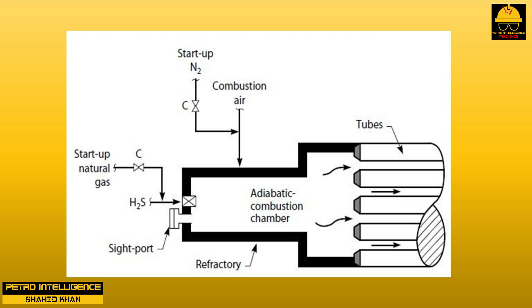Basically, the other people at the sulfur plant were head office people whom he did not trust. The reheat phase of the start-up seemed to be going quite slowly. The combustion chamber temperature crept up by 50 degrees Fahrenheit an hour, rather than the normal 150 degrees Fahrenheit per hour. To speed the reheat, he reduced the nitrogen flow. This helped, but not by much. It all seemed so odd, especially as the interior of the chamber — viewed through the sightport shown in picture — had a dazzling white appearance.